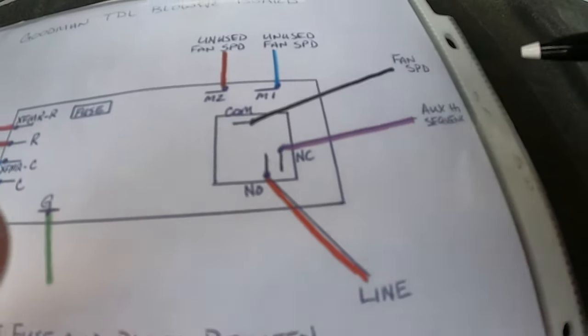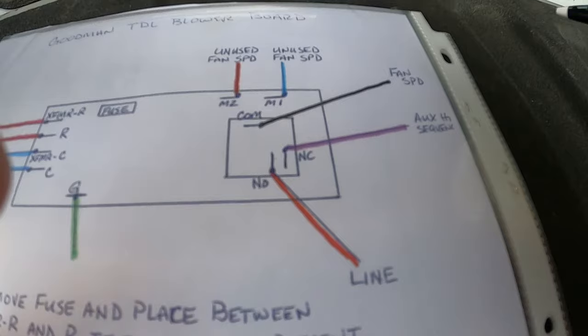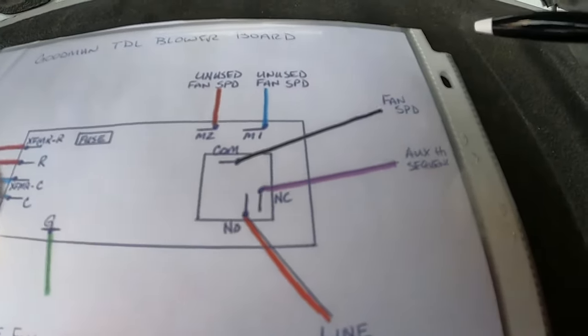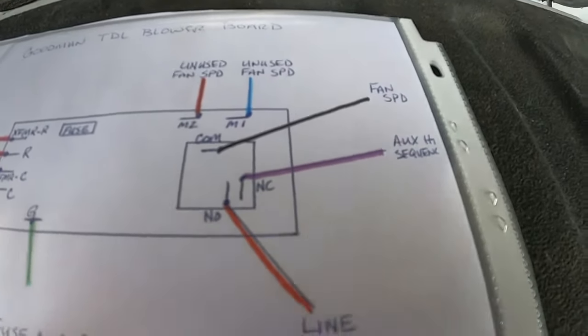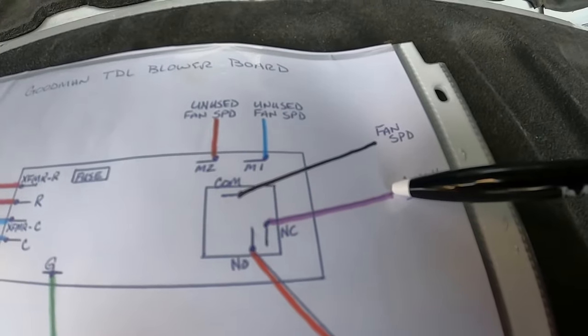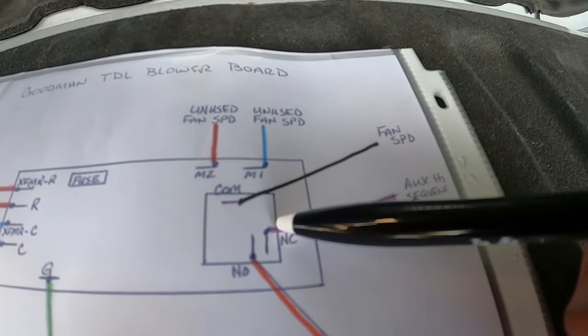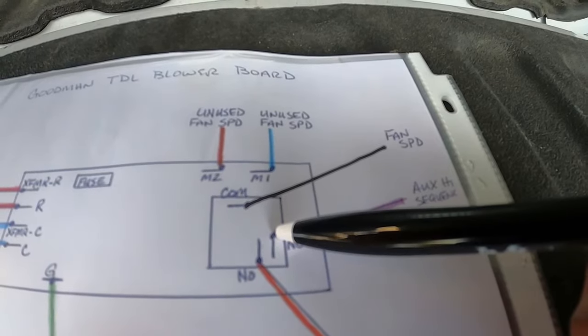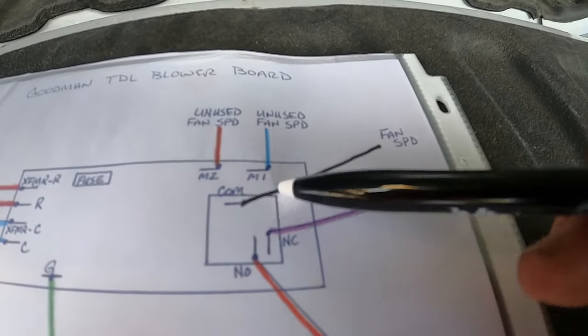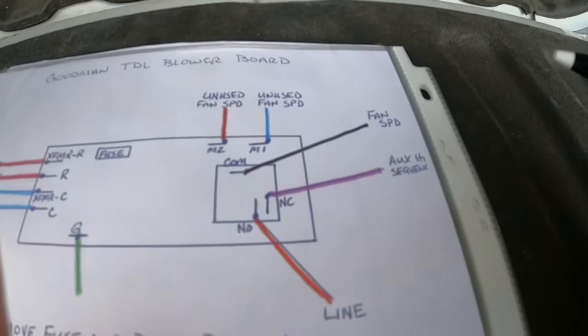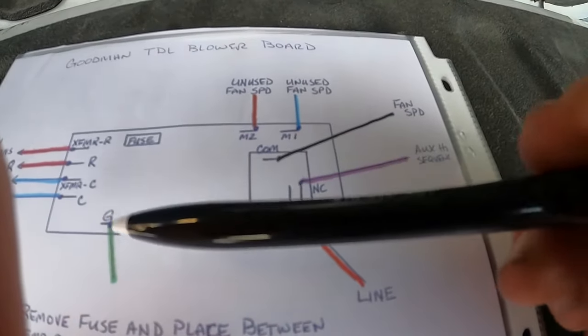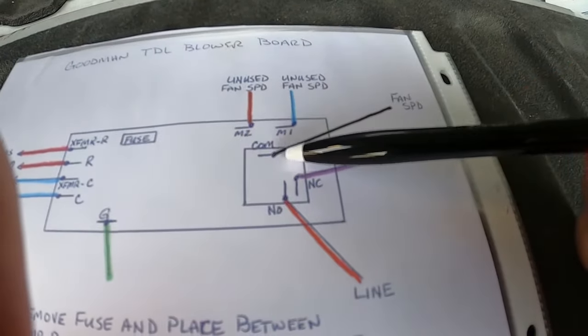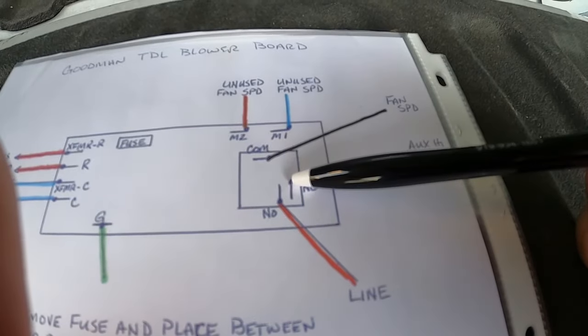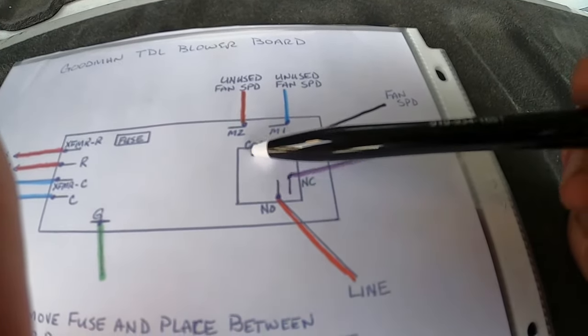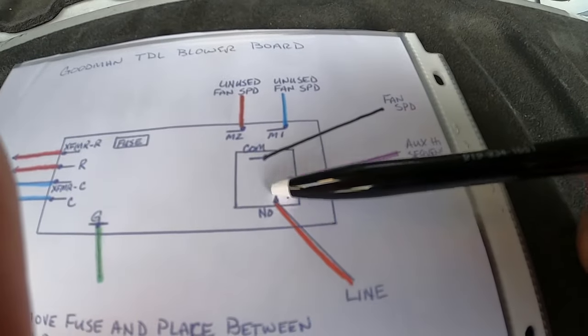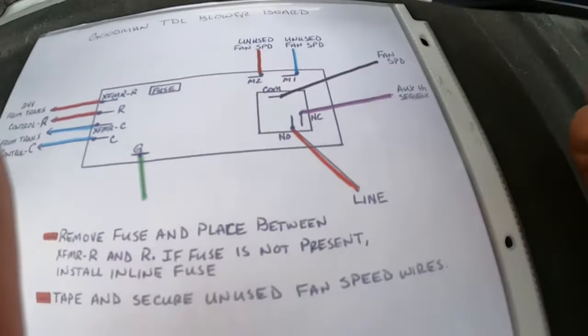So in this situation, if your emergency heat calls, you energize a heat sequencer. When that heat sequencer closes, it'll energize a bank of heat strips. That will immediately send power back to your normally closed switch on your relay, energize your blower so you have airflow while your heat strips are running. If you get a call for G, it's going to close that relay. It's going to open the normally closed switch, close the normally open switch, and now your blower is going to be powered with your incoming line voltage.